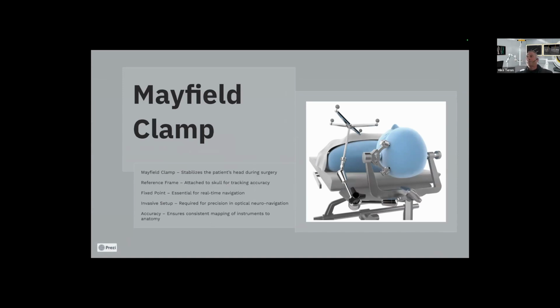Now that connection to the Mayfield clamp is our point of reference for our navigation. So we rigidly attach a reference frame, as you can see here, onto the patient's anatomy. And then through that dynamic referencing, once the registration that I mentioned earlier, where we link the virtual patient to the real patient on the table, is performed, once the system knows where the patient is, that frame is its point of reference and that frame cannot move.